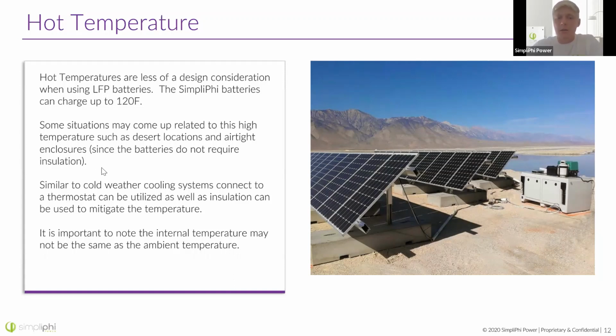So occasionally, areas like deserts and airtight enclosures with no ventilation at all will bump up against this type of temperature limit. Really, it's similar systems to cold weather - you could use a temperature sensor. The Victron devices can be programmed as far as high temperature as well, and the SimpliPhi is going to have high temperature protection as well when paired with a communicating device. So there's definitely similar ways to mitigate these, it's just not as commonly an issue.